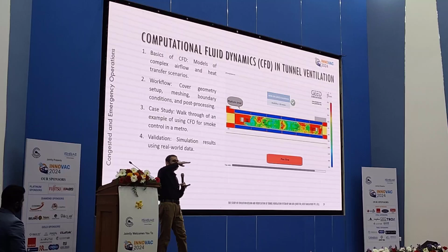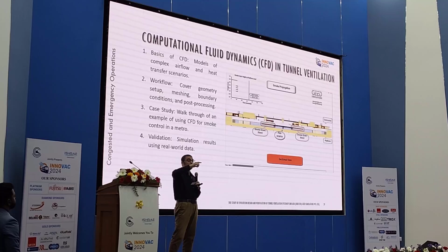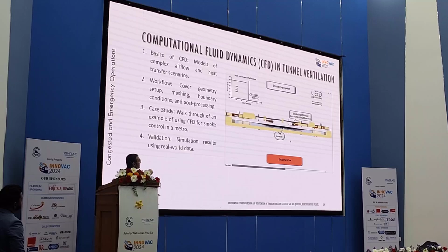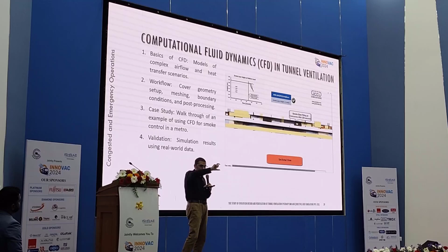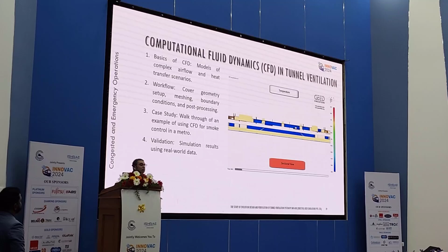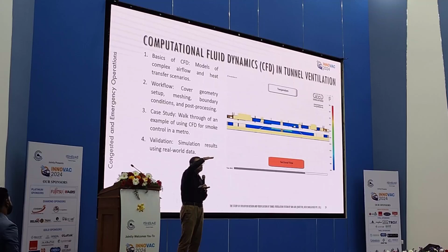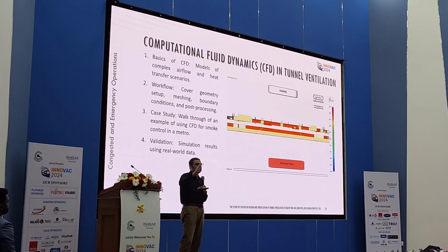You check here how the smoke at 1.2 meter height, and at 2.0 meters, average human height, is going to spread. This section shows how smoke spreads through these specific floors. We're calculating available safe egress time and required safe egress time, that is the time the smoke takes to come down to head height, during which everybody has to be evacuated. This is ASET and RSET, available safe egress time and required safe egress time.